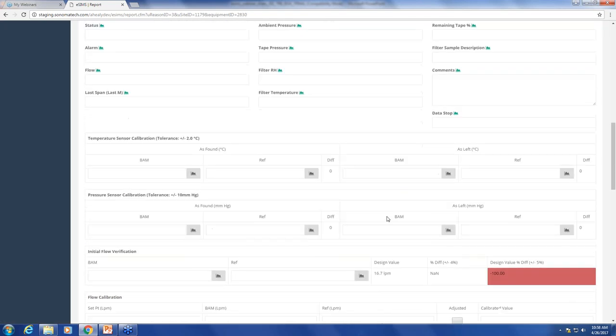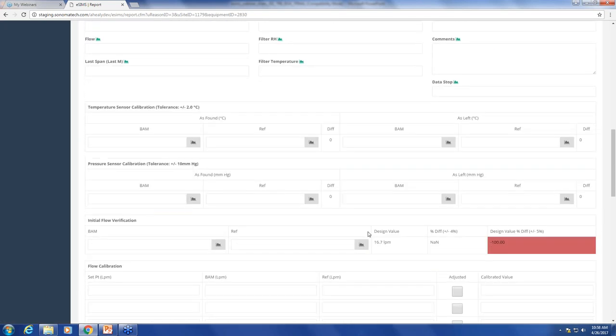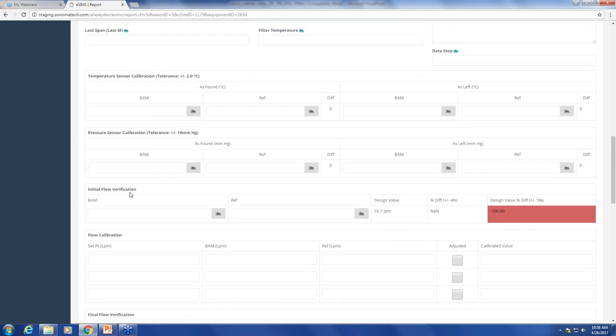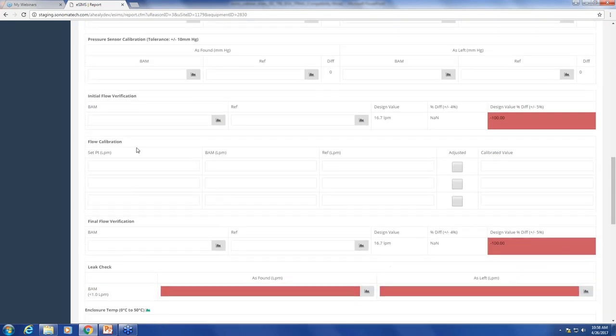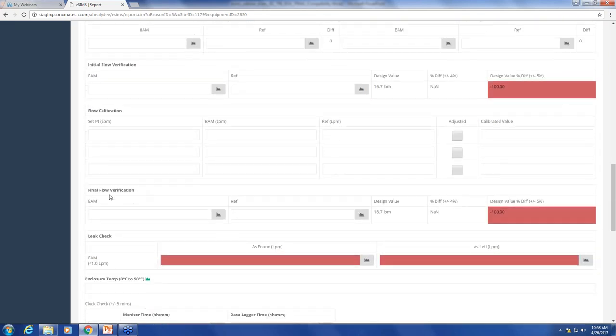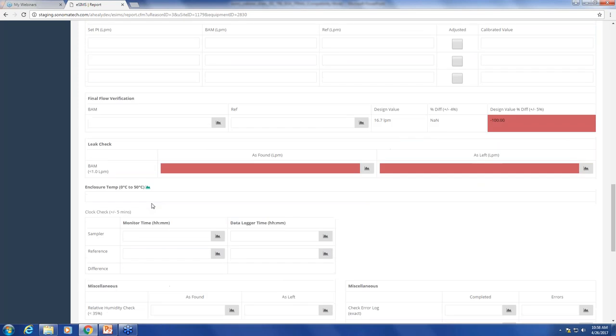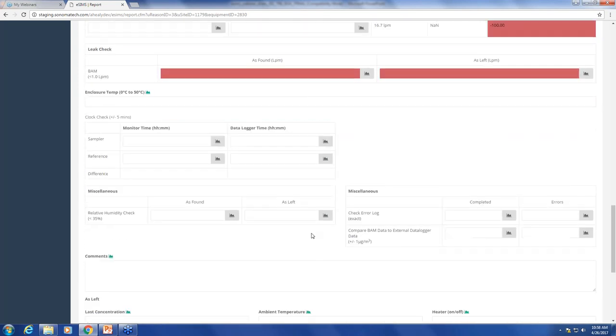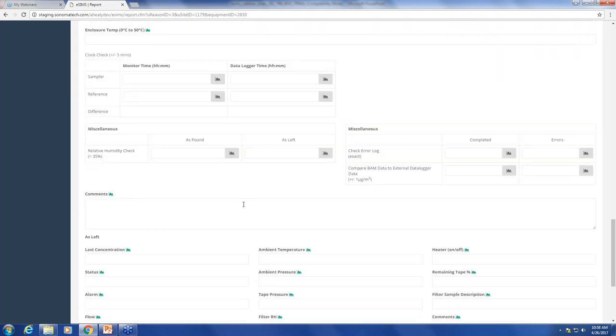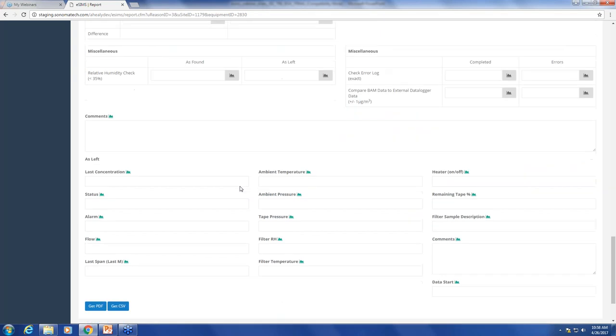If I scroll down, we get into the actual calibration of the operation here. We have our temperature cal, pressure cal, initial flow verification, flow calibration if needed, final flow verification, leak check. We have some more miscellaneous items here, and a general comment section if you want to enter any information about the overall calibration itself.